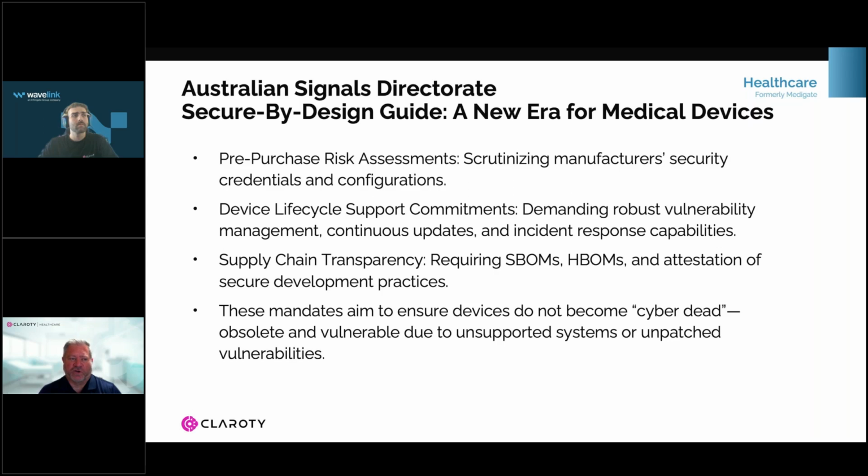The other part of secure by design is, over the life cycle of that asset, what do we need to do around making sure that there's vulnerability management, threat intelligence, updates, and incident response? Because the last thing you want is, for example, let's pick an MRI machine, an expensive machine that's probably going to have a 10 to 15-year life cycle. It's not something that you can set and forget, because at some point there are going to be vulnerabilities on the asset, either because of the way it's connected or because of vulnerabilities found in the underlying operating system that potentially cause risk. So you need to make sure that the organizations selling these devices to you have lifecycle support throughout the journey.